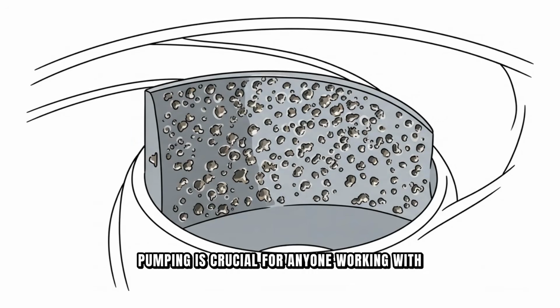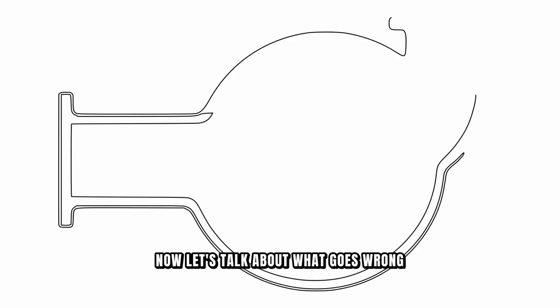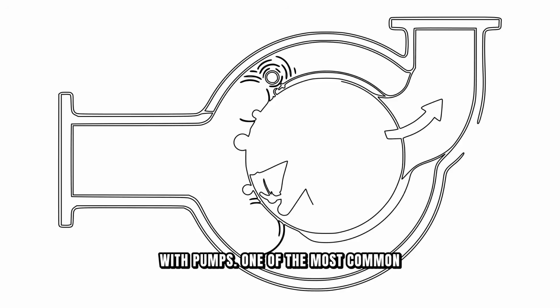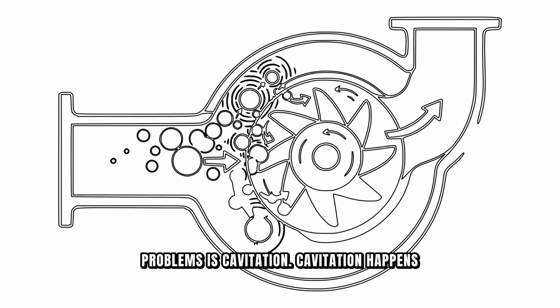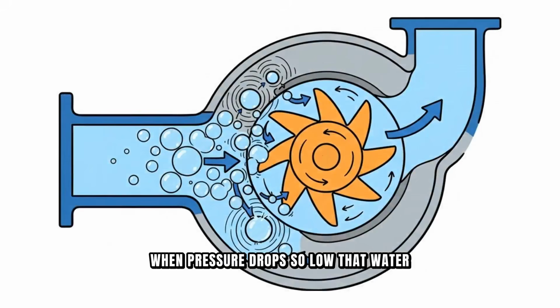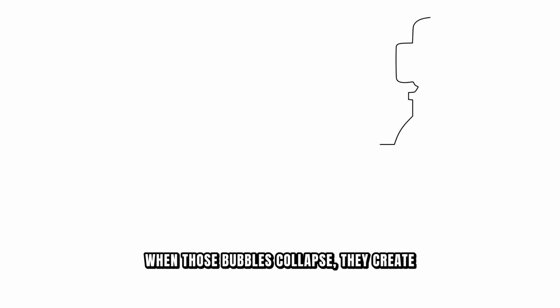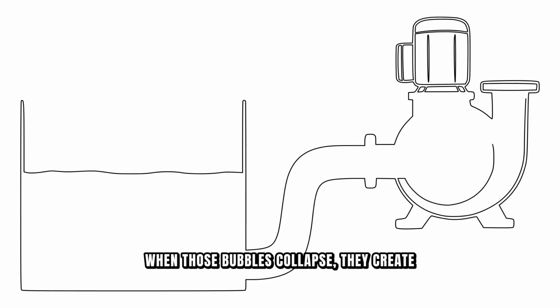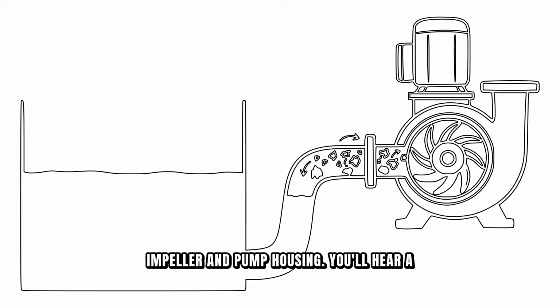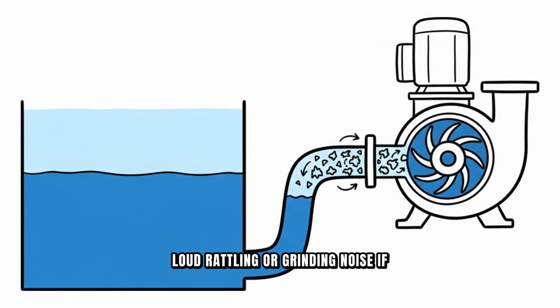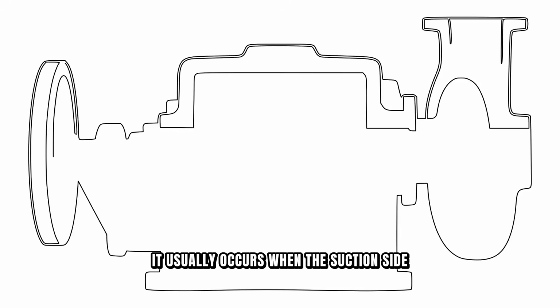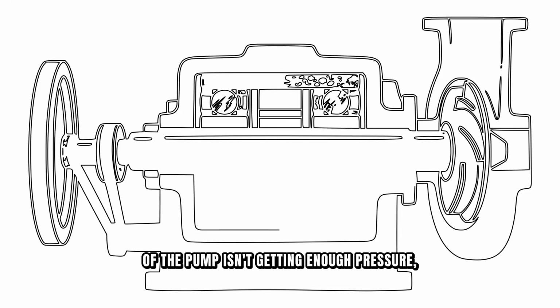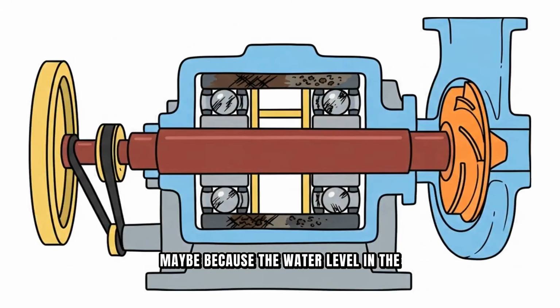Now let's talk about what goes wrong with pumps. One of the most common problems is cavitation. Cavitation happens when pressure drops so low that water actually turns into vapor bubbles inside the pump. When those bubbles collapse, they create shock waves that pit and damage the impeller and pump housing. You'll hear a loud rattling or grinding noise if cavitation is happening. It usually occurs when the suction side of the pump isn't getting enough pressure, maybe because the water level in the tank is low or the intake filter is clogged.